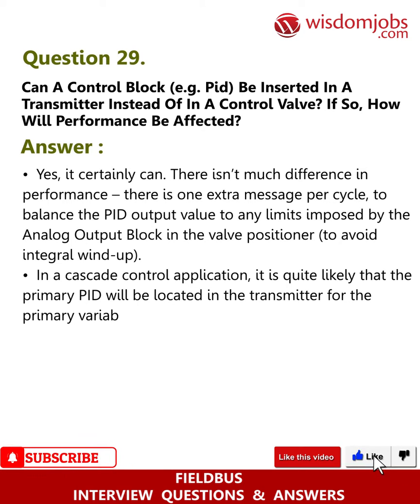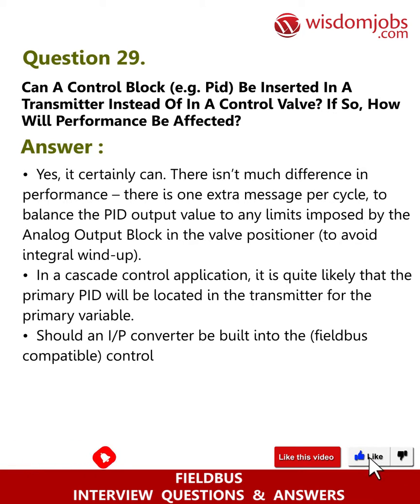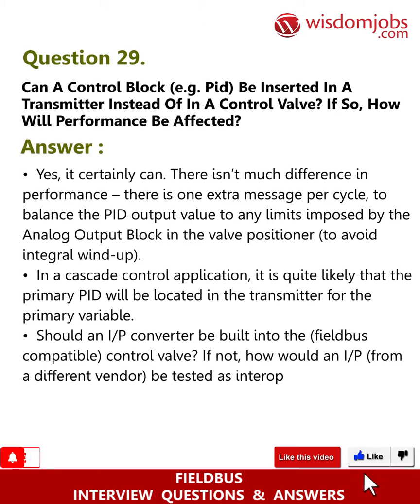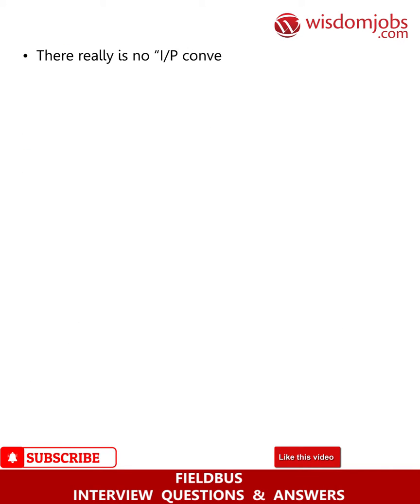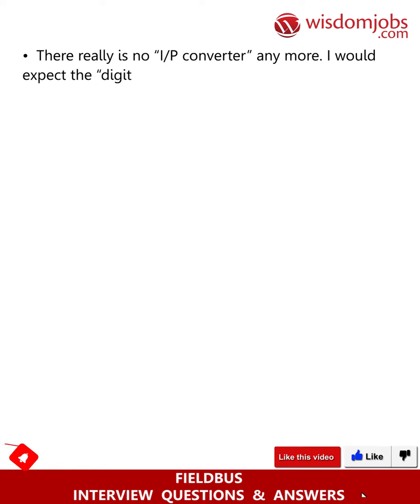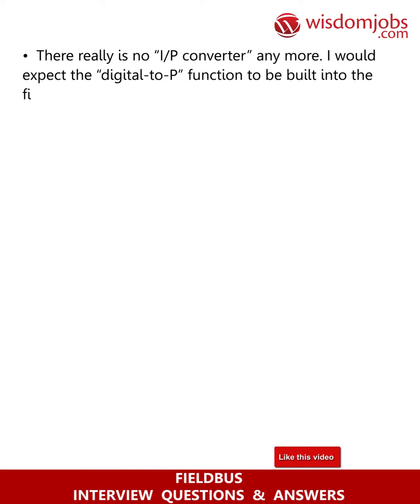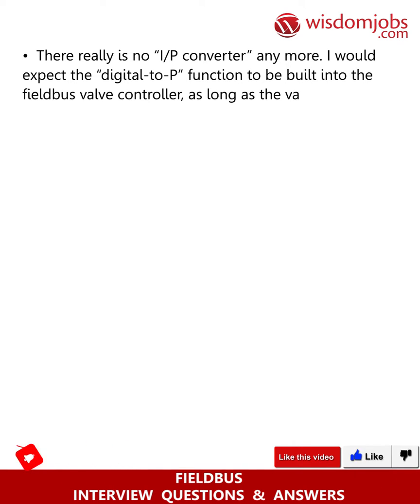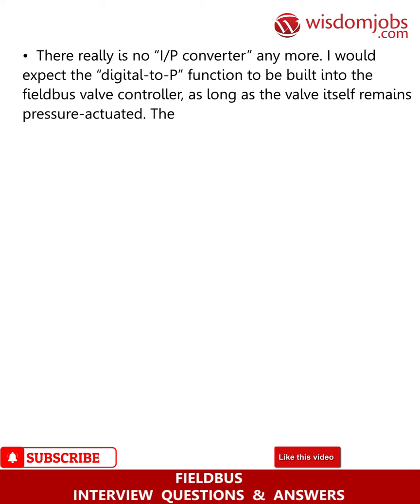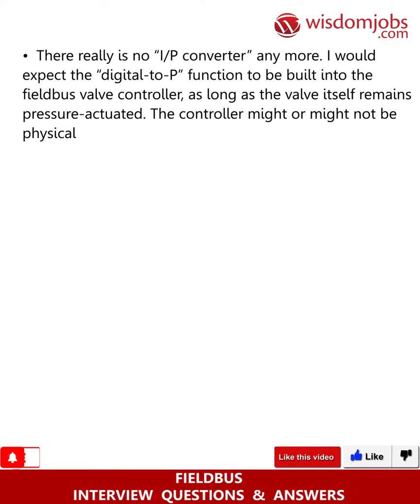Should an IP converter be built into the Fieldbus compatible control valve? If not, how would an IP from a different vendor be tested as interoperable? There really is no IP converter anymore. I would expect a digital to P function to be built into the Fieldbus valve controller. As long as the valve itself remains pressure actuated, the controller might or might not be physically mounted with the valve itself.